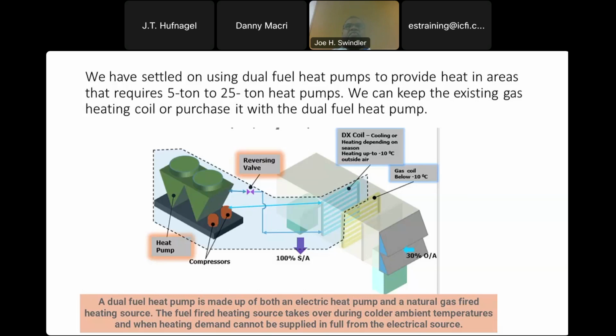So what it does is reduces your natural gas usage significantly between 50 degrees and 20 degrees. So there are dual fuel heat pumps out there, and the heat pump is used to provide heat down to 20 degrees, for example, and then you turn on your natural gas fired burner to provide heat when it's 20 degrees or lower. Next slide.